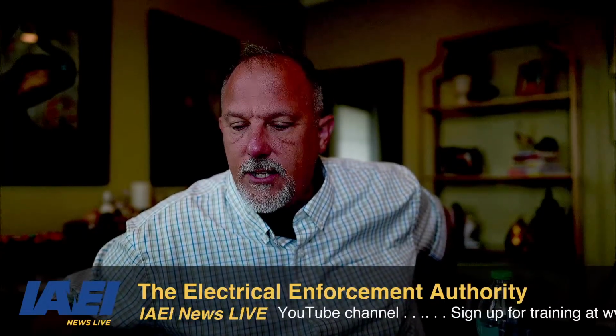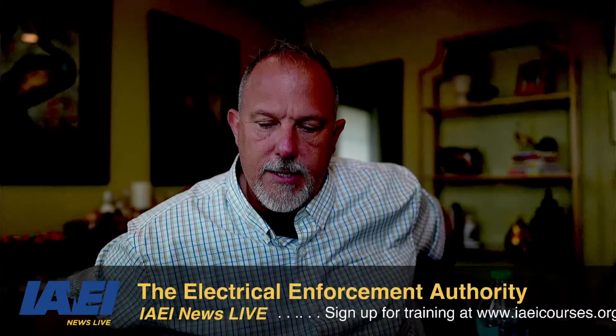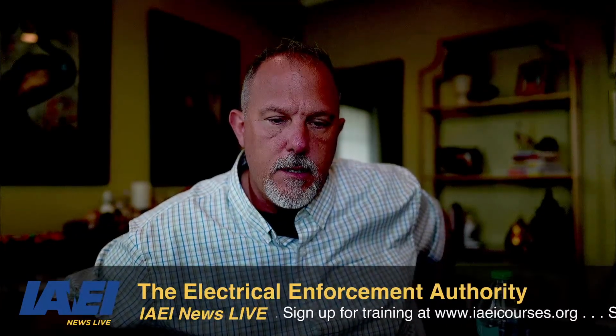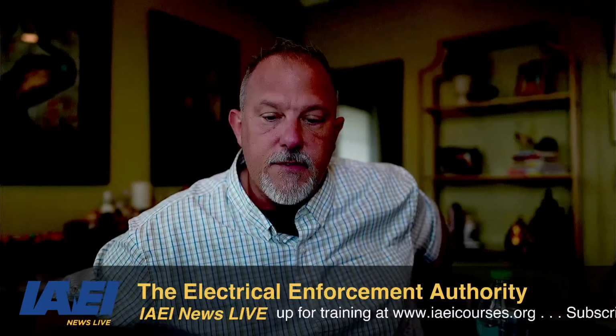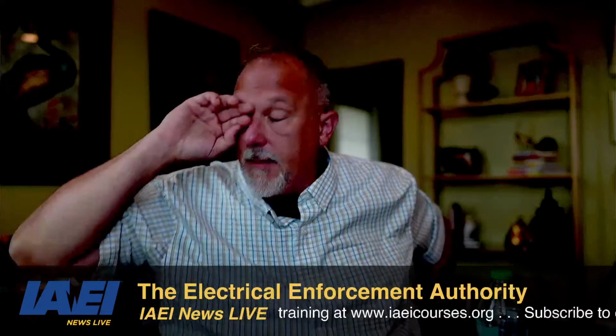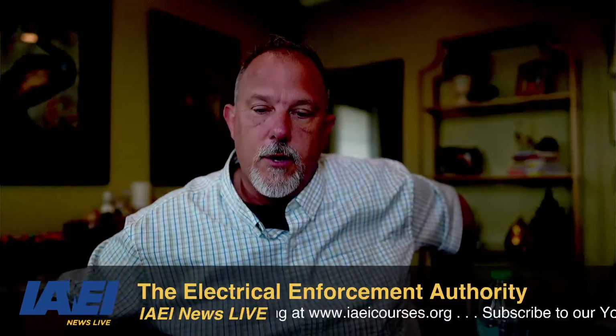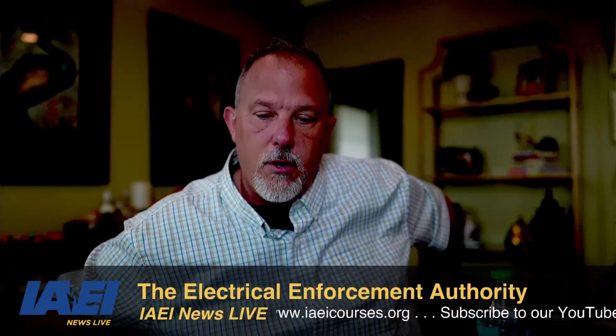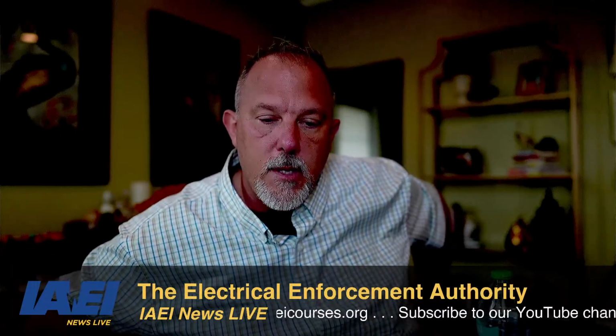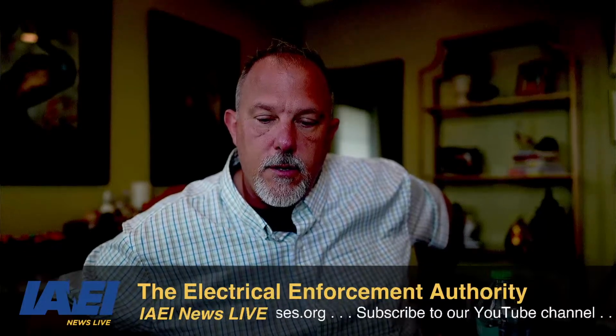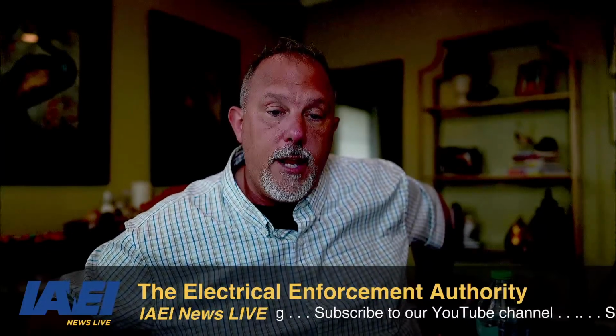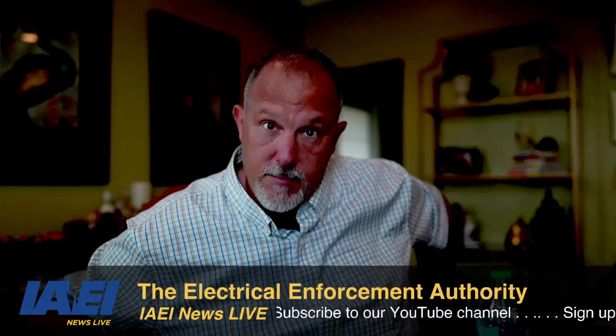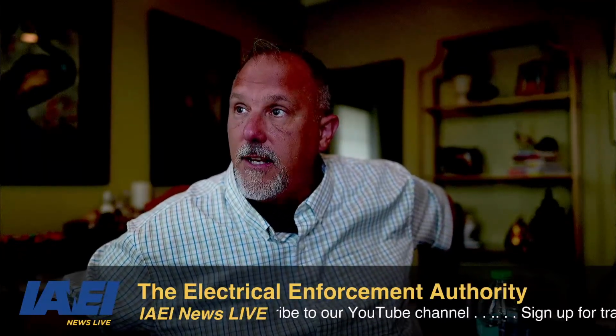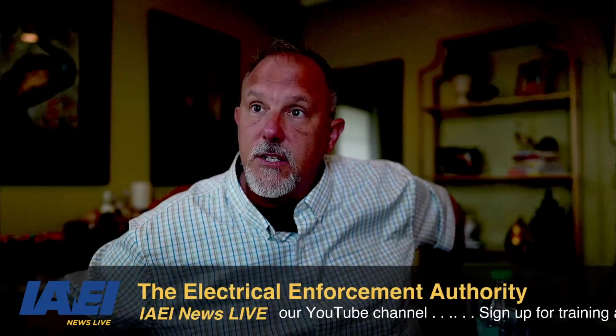In section 690.9b, in every place used in 1 and 2, overcurrent devices. Oh, man, did I miss that one? Yeah, I got overcurrent protective devices shall be rated. And then, yep, so I got that, Dawn. We are golden. I believe we've got all of the areas that we need to clean up, and nothing in 690.9, in my opinion, and the way we use the term conflicts.